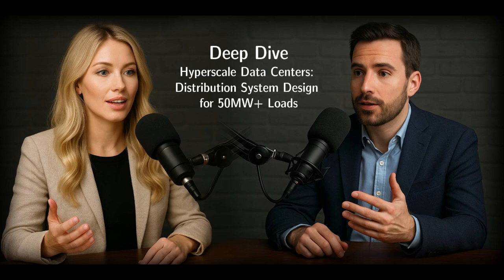Okay. Data centers demand incredibly fast fault clearing, often less than 3 cycles, especially for faults on the transmission or sub-transmission system feeding them. Any longer, and their sensitive equipment can trip offline. 3 cycles. That's fast. Very fast. It usually requires communication-assisted protection schemes, often using dedicated fiber optic channels between relays. You also typically need more sophisticated protection, like differential protection for critical transformers and the main feed lines. And seamless integration with the customer's own protection system is vital.